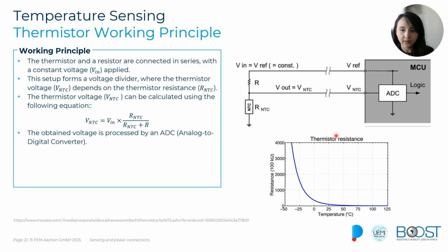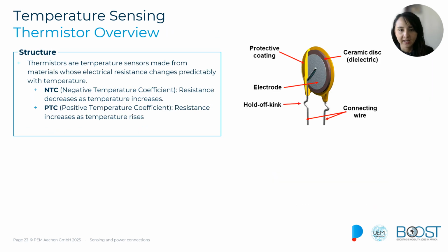As we can see here, the resistance of the thermistor changes in a nonlinear way with temperature, and because of that it usually requires advanced calibration, or in the processing of that information we need lookup tables to accurately relate the change in temperature with the change in resistance value. So this is one of the limitations of this sensor.